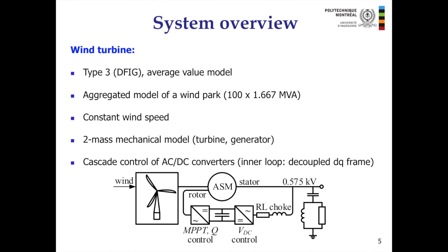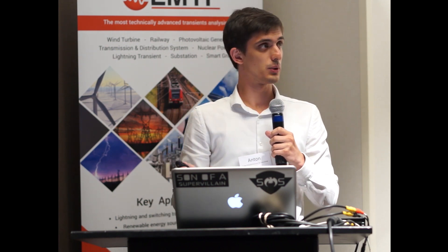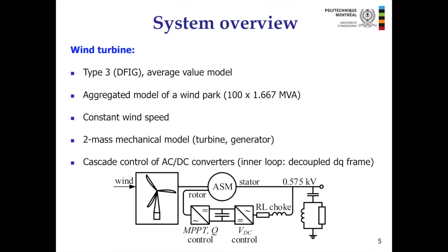Taking a closer look at the system, starting with the wind farm: it's a DFIG induction generator. In this simulation we use an average value model, and this is an aggregated model of a wind park with 100 smaller wind turbines of 1.67 MVA each. We use constant wind speed and a two-mass mechanical model — one part is the turbine and the other is the generator. For the control part, there is an AC-DC-AC converter using standard cascade control structure, with an inner current control loop and an external loop for DC voltage control or MPPT for the wind farm side. It uses decoupled DQ control.